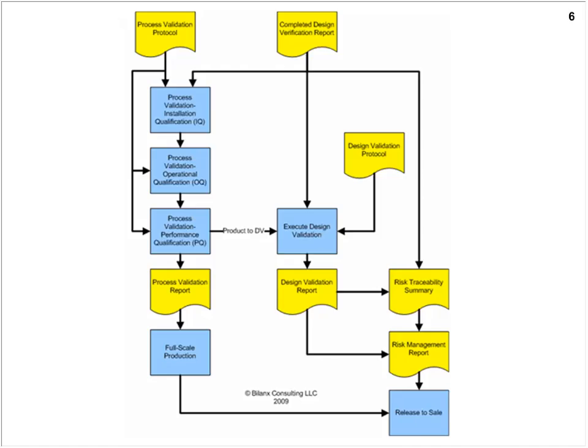We do have to complete these other phases, the verification of the design and the validation of the process, the validation of the product, and also the verification of our implementation and effectiveness of our risk control measures. So all these things occur late in the process of the design of the product, but they must be completed prior to release to sale.